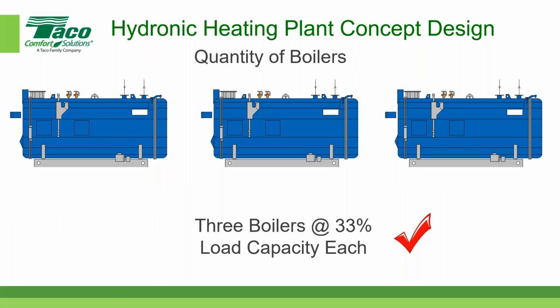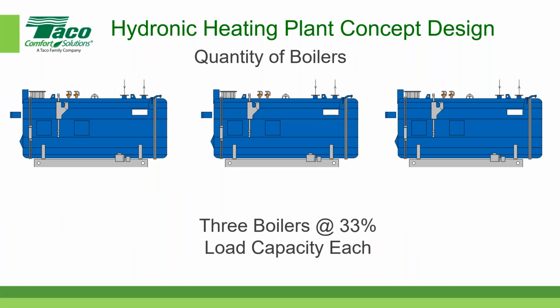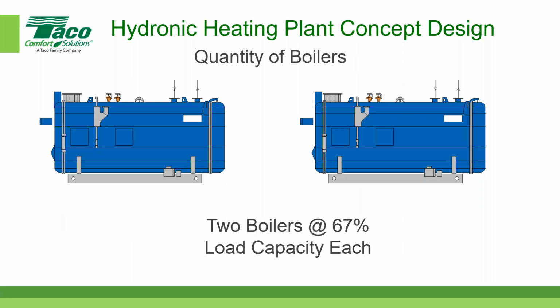Someone said, why set 67% boiler capacity? You mean in terms of these 2 guys here? Yeah, 2 boilers at 67% capacity each? Well, the logic there is that, again, between 75 to 95% of the hours in the year, you're going to have a load that's probably less than 67%. So under those circumstances, which is the majority of hours in the year, your plant becomes 100% standby.